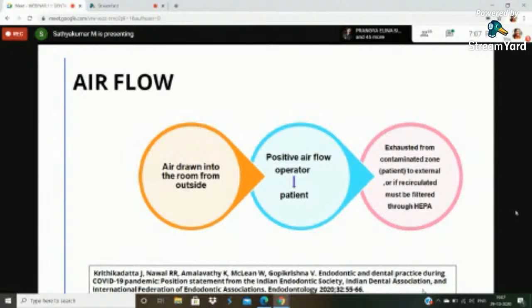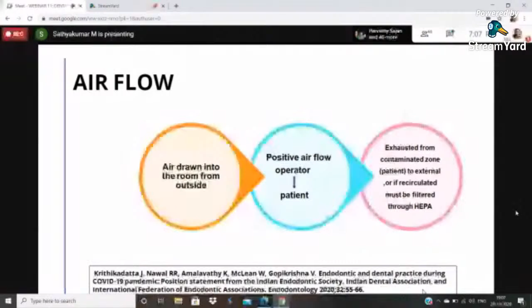When I say airflow, air is drawn into the room from outside - this is what happens initially. And when I say positive airflow, the direction of the airflow is going to be from the operator to the patient, and then it is directed and exhausted from the contaminated zone, from the patient to the external. Or if it is recirculated, it must be filtered through a high efficiency particulate air purifier.